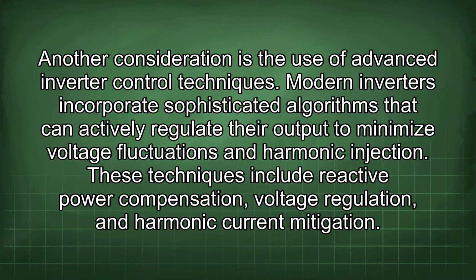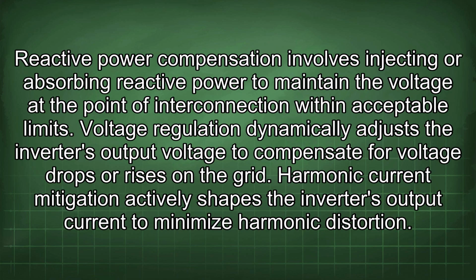Another consideration is the use of advanced inverter control techniques. Modern inverters incorporate sophisticated algorithms that can actively regulate their output to minimize voltage fluctuations and harmonic injection. These techniques include reactive power compensation, voltage regulation, and harmonic current mitigation. Reactive power compensation involves injecting or absorbing reactive power to maintain the voltage at the point of interconnection within acceptable limits. Voltage regulation dynamically adjusts the inverter's output voltage to compensate for voltage drops or rises on the grid. Harmonic current mitigation actively shapes the inverter's output current to minimize harmonic distortion.